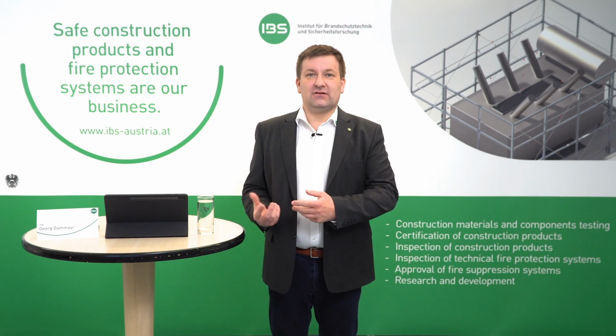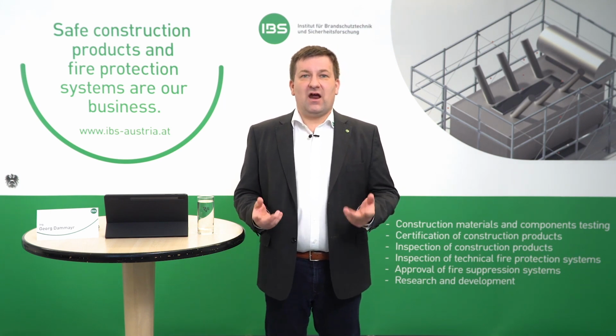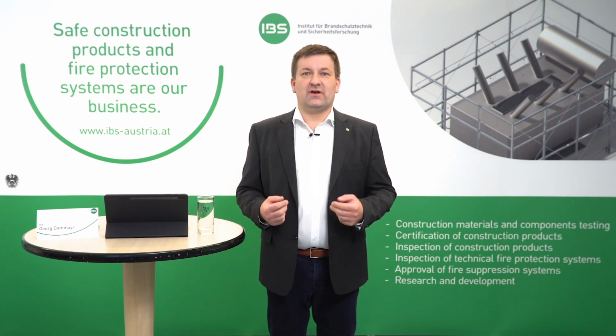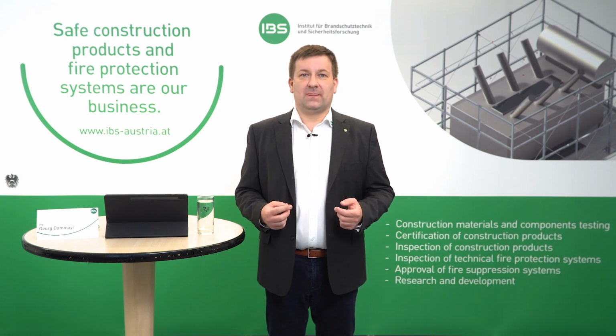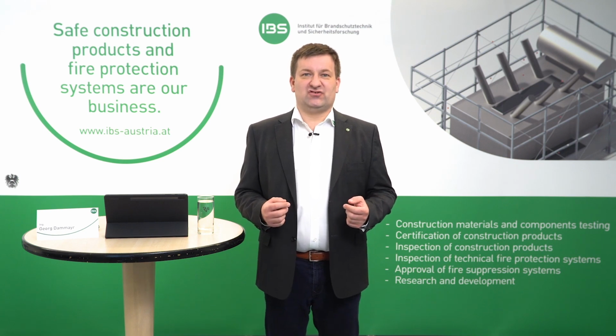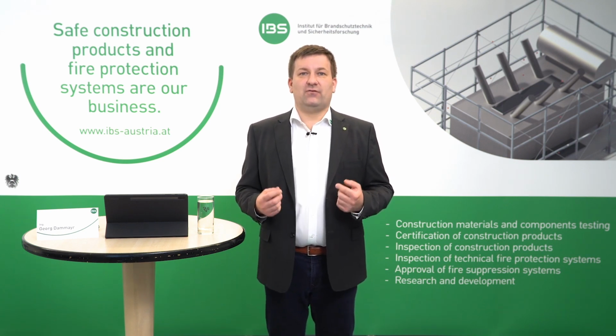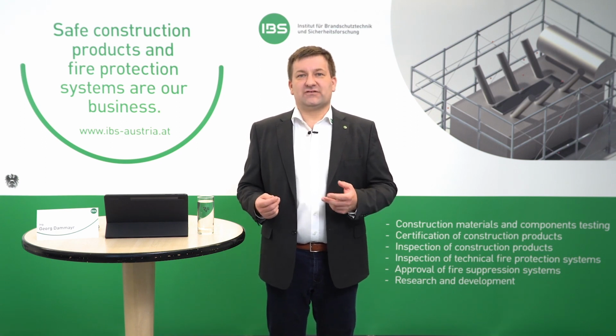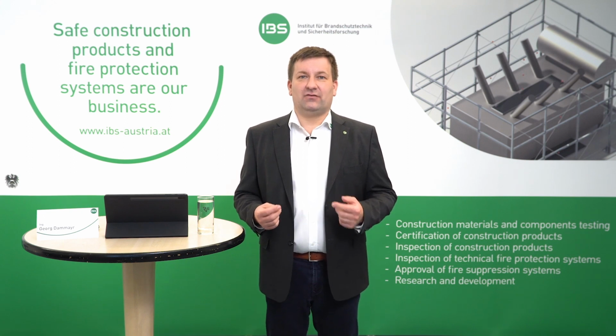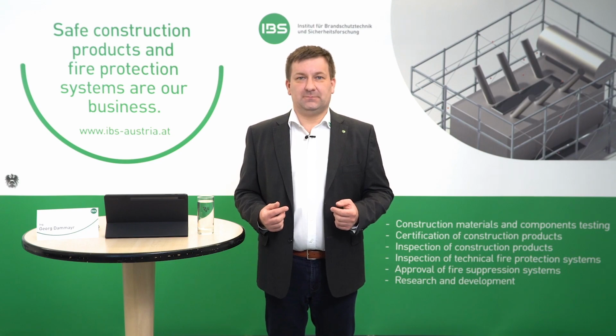Do you operate on the international market? Wonderful! So are we, from South Africa to the Middle East or overseas. We carry out approval testing for products for various markets. For example, a low-pressure water mist fire suppression system for oil-cooled transformers up to 132 kV was tested at a test site in South Africa for one of our customers from Poland.